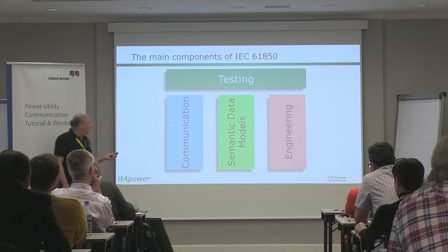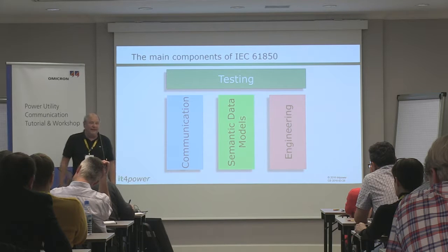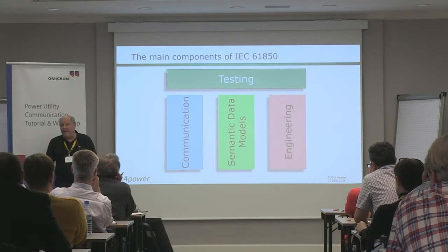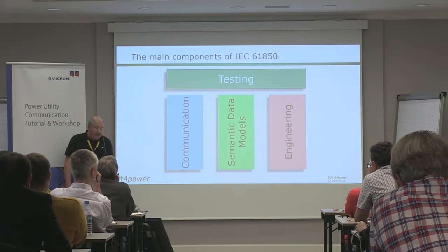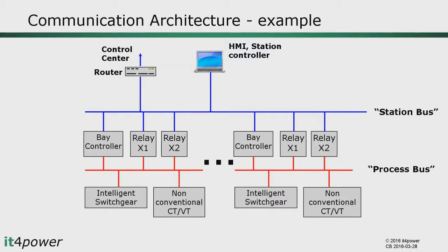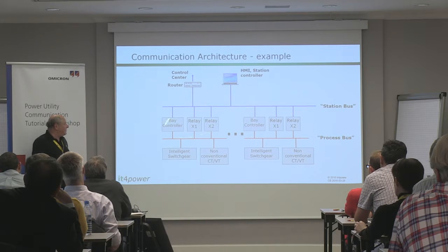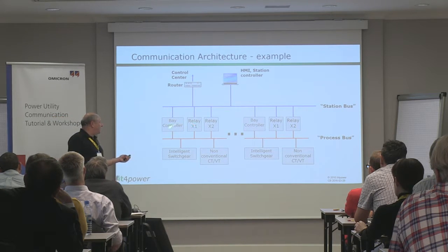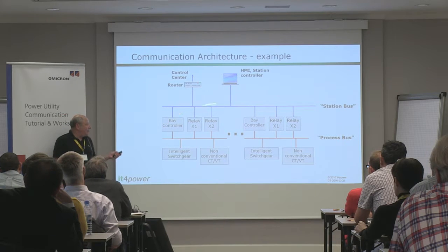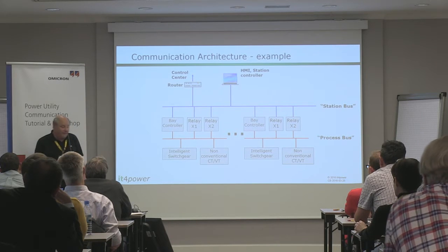Let's take a closer look at these three elements. Starting with communication, here is a typical communication architecture as supported by 61850 in a substation. At the station level we have HMIs, station controllers, and gateways or routers that interface to the control center. A station bus connects these station-level devices with bay-level devices — protection devices and bay controllers — and also supports communication between bay-level devices.